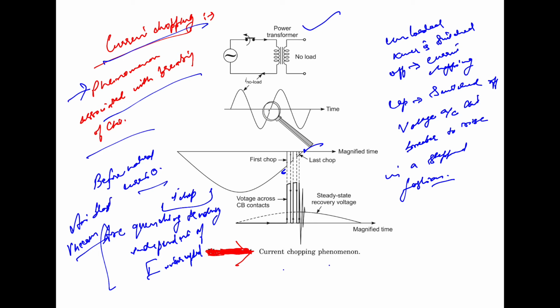In these type of circuit breakers, arc quenching tendency is independent of the current which is being interrupted. Now, as soon as current is forced to zero, the energy stored in the magnetic field of system inductance reappears as the energy in the electric field of the system capacitance. And the capacitance, as we have also discussed earlier, is very low. Hence, a small value capacitance needs to be charged to a very high voltage, designated as V res. So we can say that restriking voltage accommodates the given amount of energy.